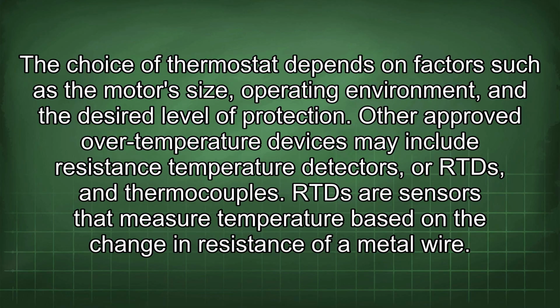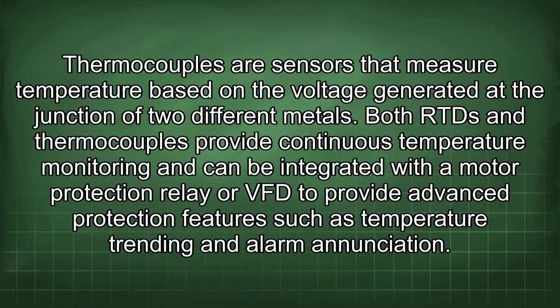Other approved over-temperature devices may include resistance temperature detectors, or RTDs, and thermocouples. RTDs are sensors that measure temperature based on the change in resistance of a metal wire. Thermocouples are sensors that measure temperature based on the voltage generated at the junction of two different metals. Both RTDs and thermocouples provide continuous temperature monitoring and can be integrated with the motor protection relay or VFD to provide advanced protection features such as temperature trending and alarm annunciation.